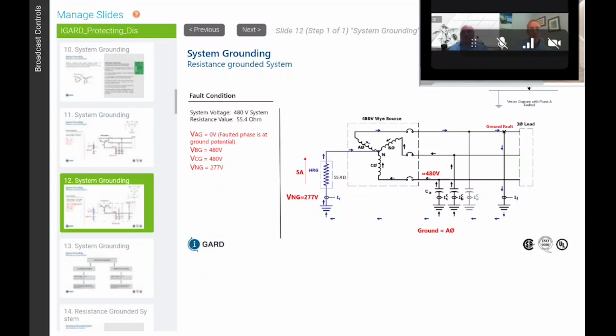What we do sometimes is put the mechanical loads on a resistance grounded system, so have an isolation transformer to take care of the comfort loads, shall we say, of air conditioner and heating, because when you have a solidly grounded system and you have a distributed neutral, you have a lot of line to neutral loads. You could put in an isolation transformer to handle only the mechanical load. So even if you have a ground fault on the solidly grounded system, the mechanical loads will continue to work.